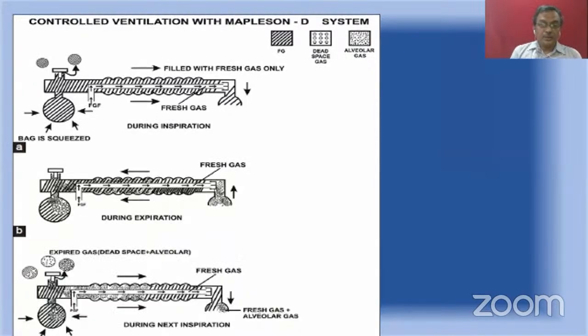And during the next inspiration, what happens is this dead space gas and alveolar gas plus fresh gas collected in the reservoir bag is pushed through the valve. At the same time, some amount of alveolar gas which was inside that outer tube will be pushed back. So a very important point to be remembered is that during controlled ventilation also, some amount of alveolar gas goes back to the patient. So Mapleson D system is a system with some amount of rebreathing.